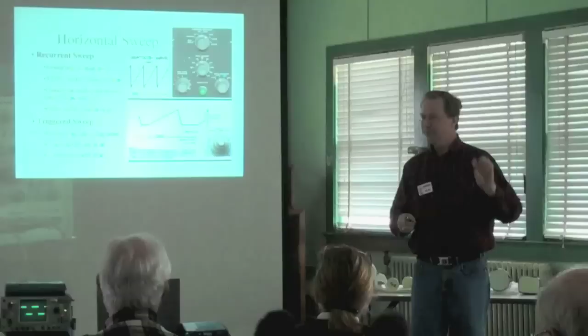I brought this up because it's the biggest difference you'll see with the service grade scopes. Some of the older ones won't have the calibrating feature. Also, those same scopes with the recurrent sweep usually don't have a calibrated vertical input either. Instead of a volts per division control, they'll often just have an input attenuator that says 1x, 10x, or 1000x, with some vernier gain control. So you won't have a calibrated vertical or horizontal. But that's another way to look at it: do you have something that says volts per division, or do you just have something that says input attenuation?